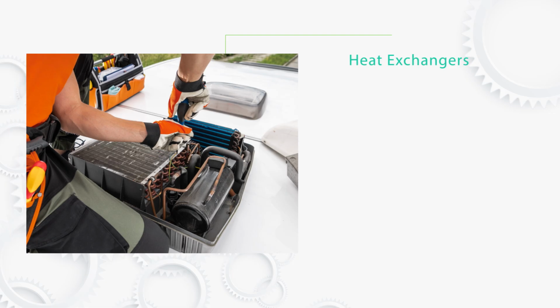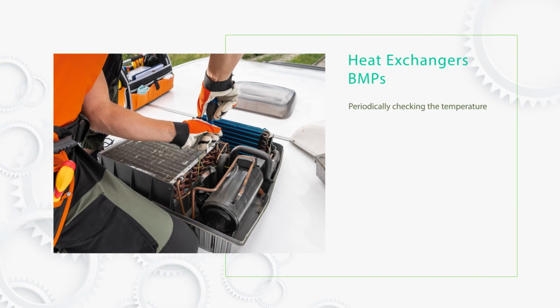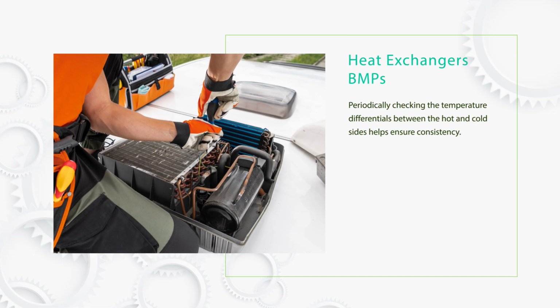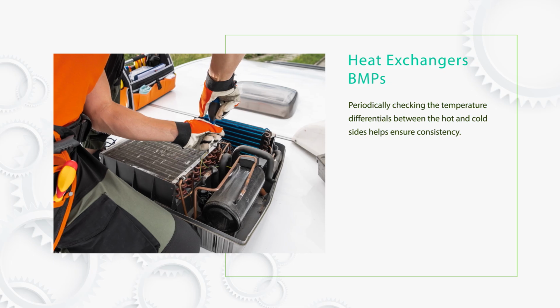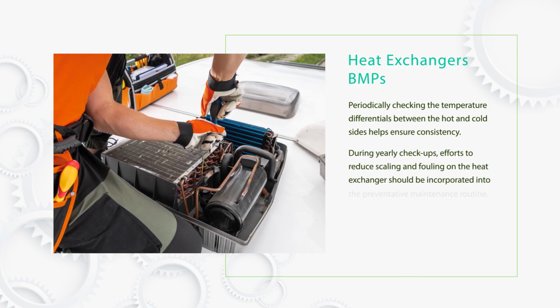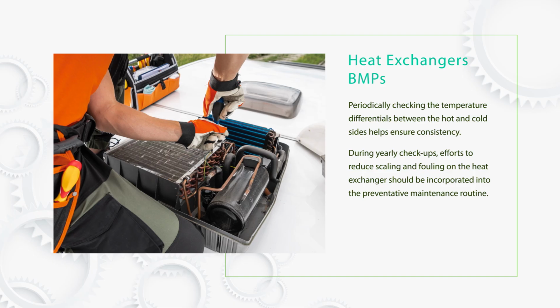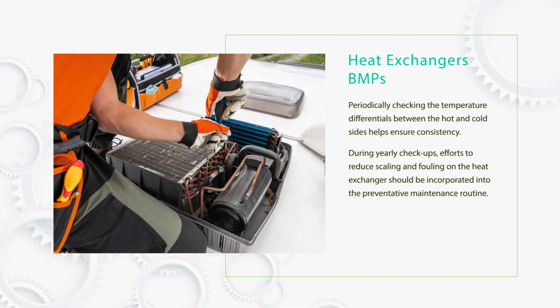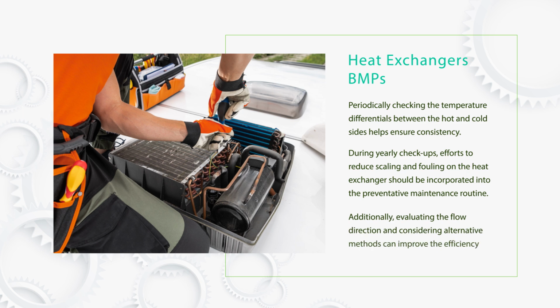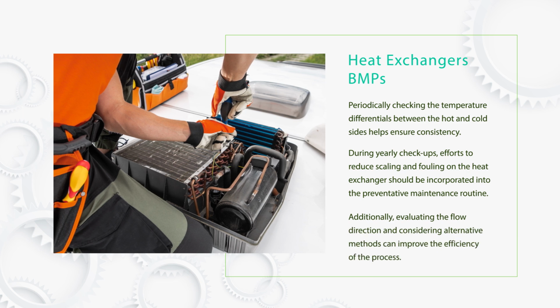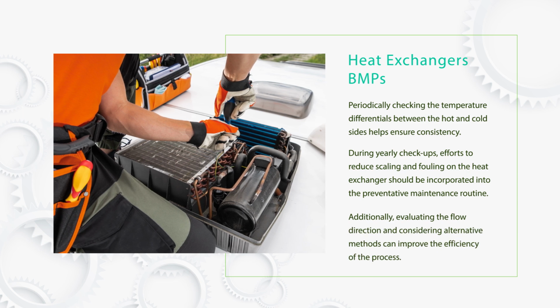Maintaining a preventative maintenance schedule is essential for optimal performance. Periodically checking the temperature differentials between the hot and cold sides helps ensure consistency. During yearly checkups, efforts to reduce scaling and fouling on the heat exchanger should be incorporated into the preventative maintenance routine. Additionally, evaluating the flow direction and considering alternative methods can improve the efficiency of the process.